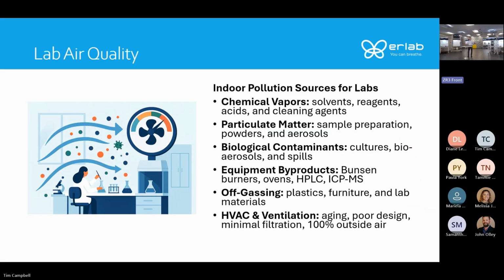Now think about a lab space where you're working every day. You're using chemicals. You're producing chemical vapors from everything you're using in the lab space. You may be producing particulate matter. You may be doing grinding. You may be using powder to do sample prep. You have equipment in there that is constantly using chemicals, and whether it could be vented outside or it may just be venting into the lab space, you're depending on your air changes to remove those chemical vapors and odors. So over time, that can build up in it.